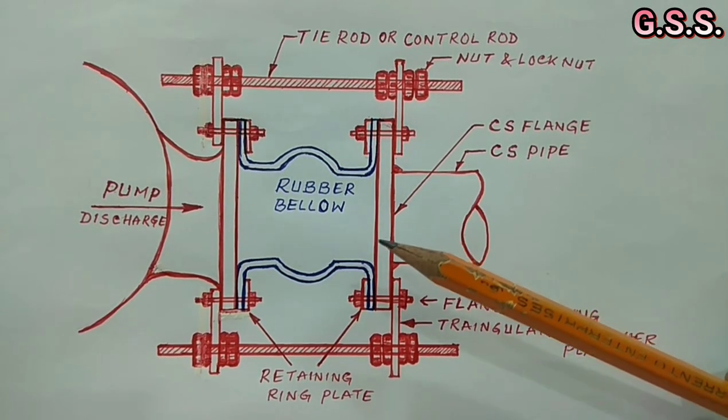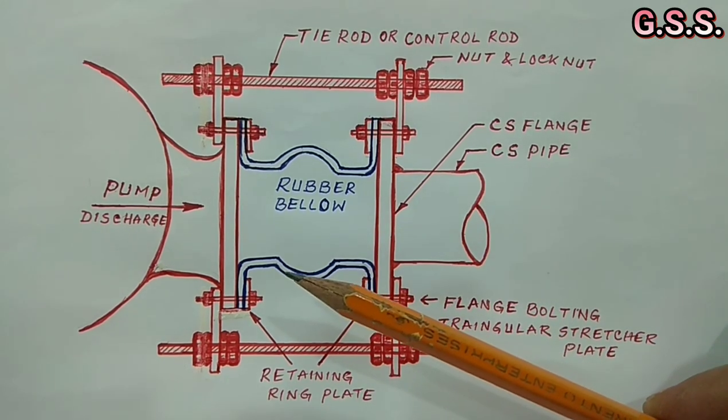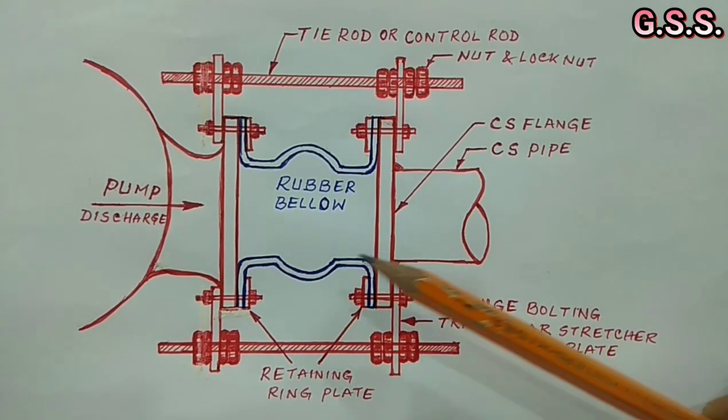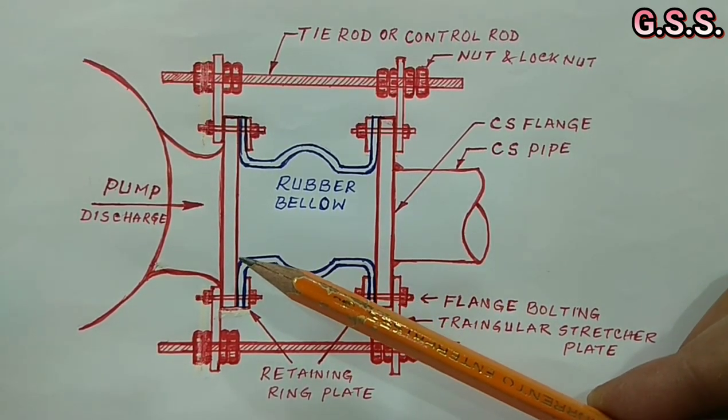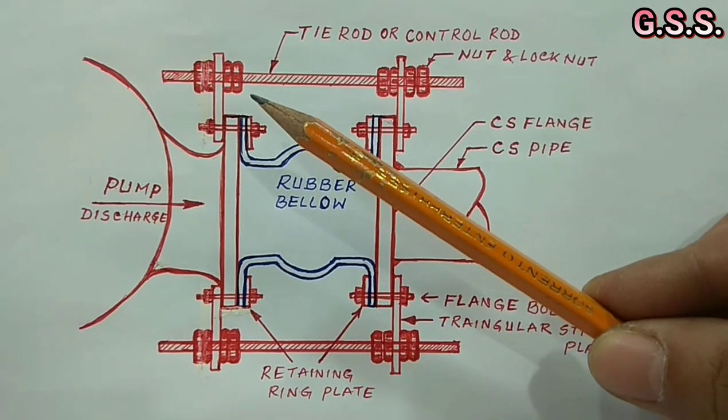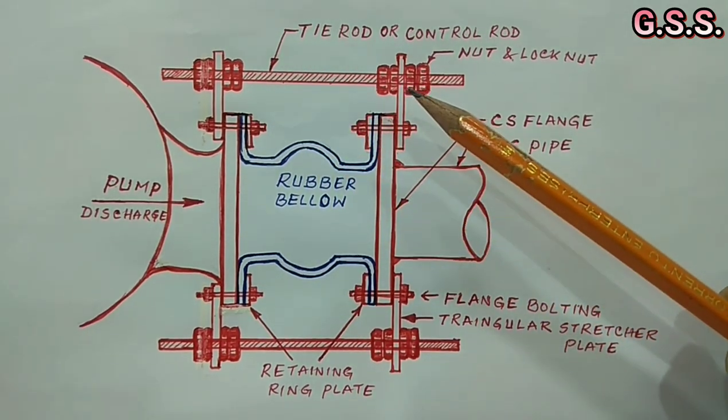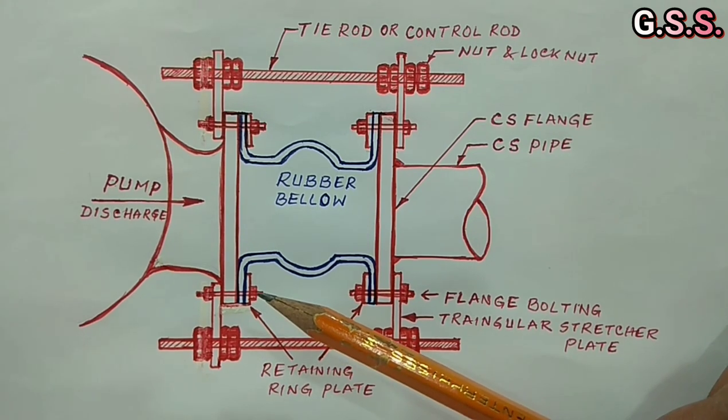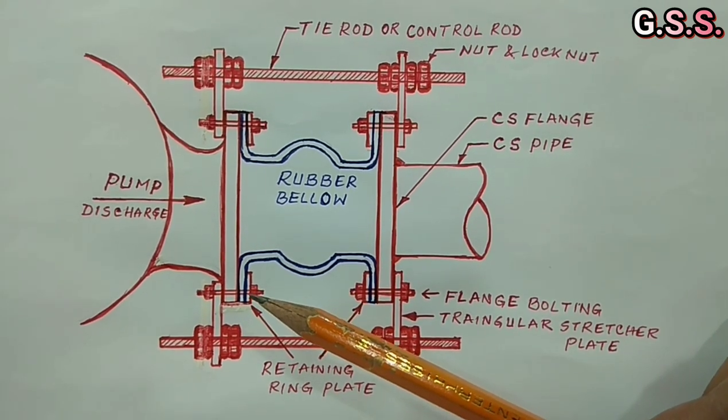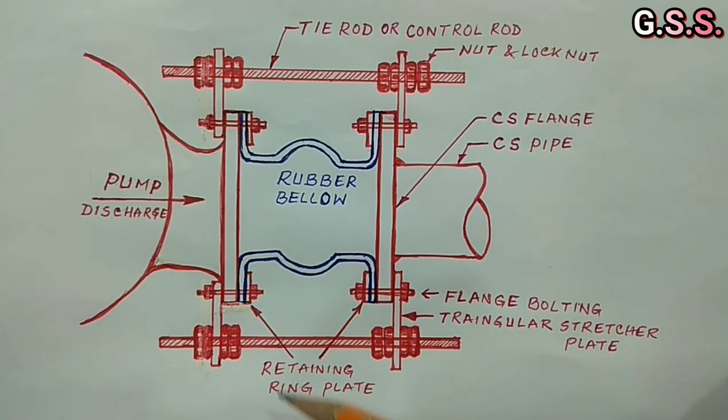First, rubber bellow is installed in between pipe flange and pump nozzle keeping tie rod nuts loose. Then pump nozzle side flange bolts are tightened with curved retaining ring plate having bolt holes.